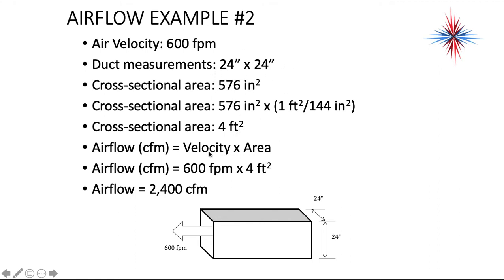We have an airflow CFM of velocity times the area. So we have 600 feet per minute times 4 square feet. So our airflow is 2,400 CFM in this example. Again, we measure the velocity, we measure the duct work, we calculate what our airflow is.